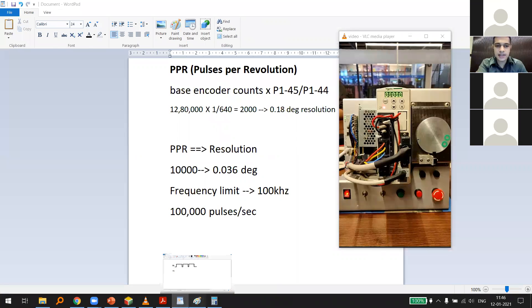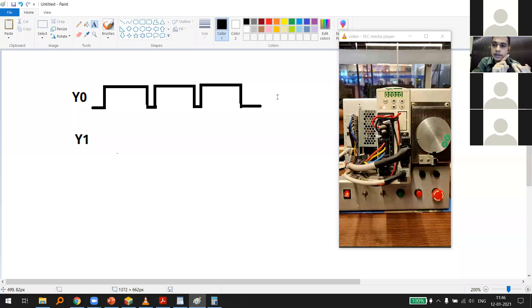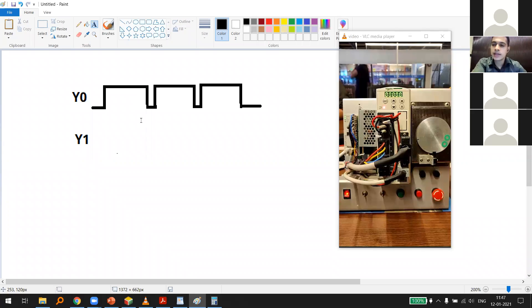The objective of this pulse output block is to move the servo. There are two things to achieve: the position — how much the servo will rotate — and the speed at which it will rotate. Position is simply the number of pulses given. Speed is the frequency at which those pulses are given.